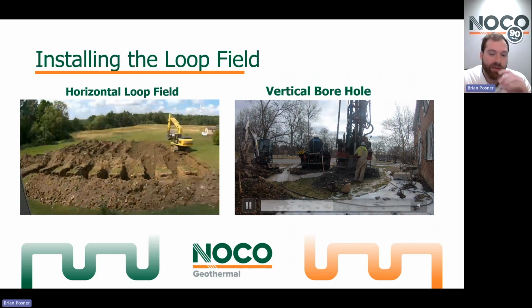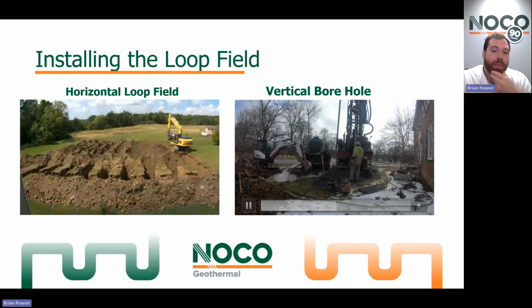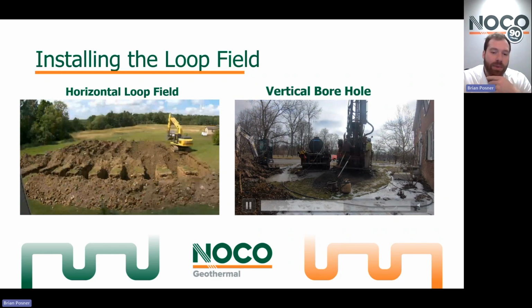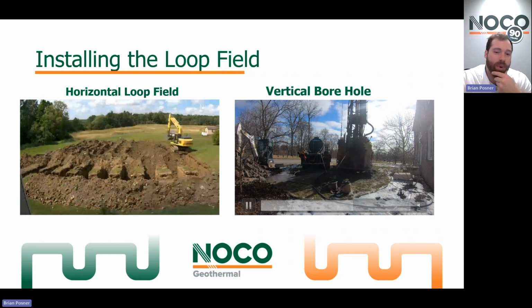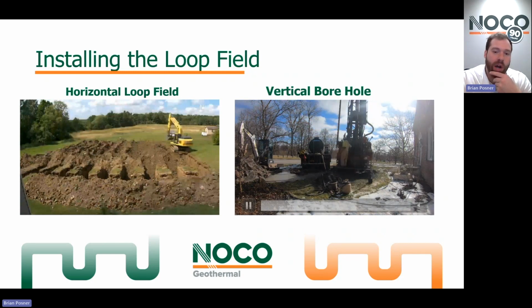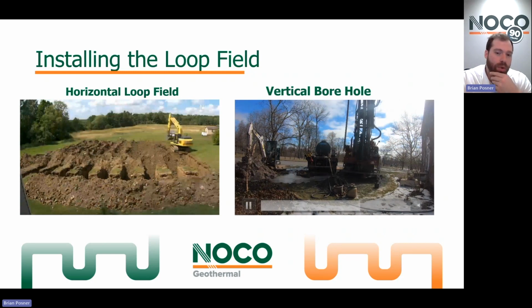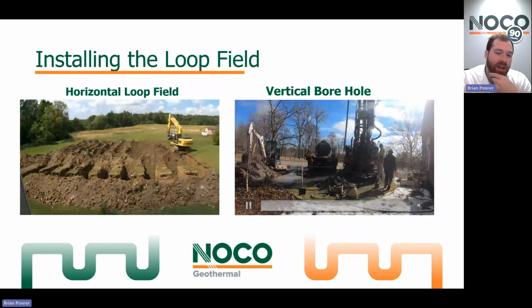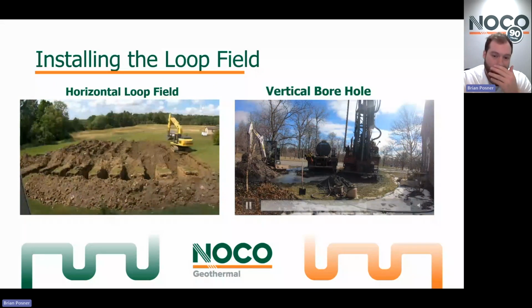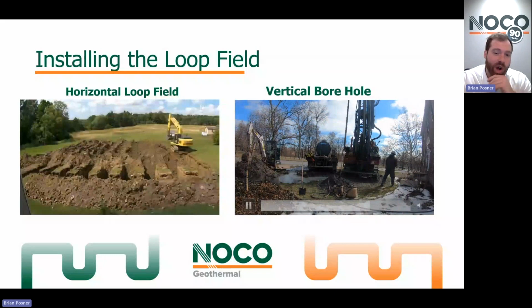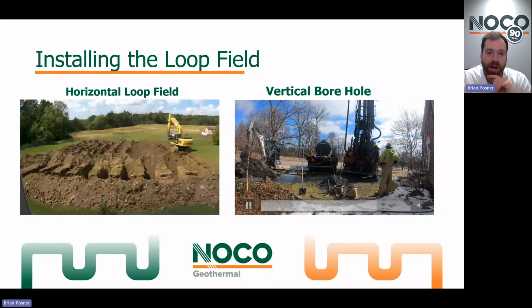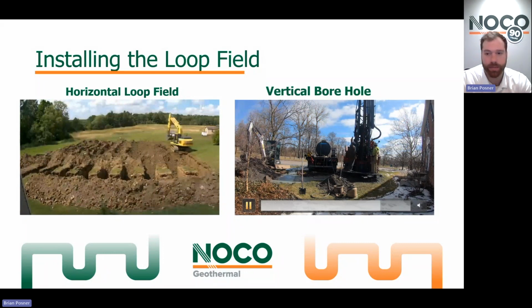Once that gets to 500 feet deep, they will drop the loop of piping into it. They will grout the hole to fill that empty space between the loop and the steel casings with thermally conductive grout. And at that point, they can start running a water antifreeze mix through the piping to do pressure testing and conductivity testing. This all gets done before the loop is connected to your home or your business to ensure that there's the thermal exchange there that the heat pump will require.